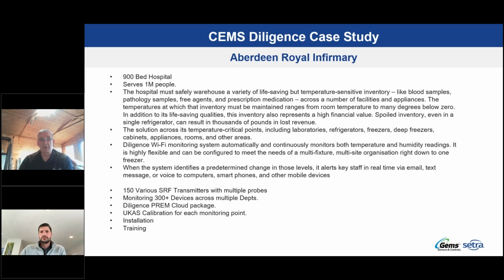They have calibration on each of their points up to ISO 17025, so they have us come on site in the UK and certify. In other territories, a third-party calibration company would come in and calibrate the sensors themselves, the actual individual probes, and produce a NIST certificate in the US to calibrate the devices on site. We also provide training, either in person or via a webinar or Teams discussion.